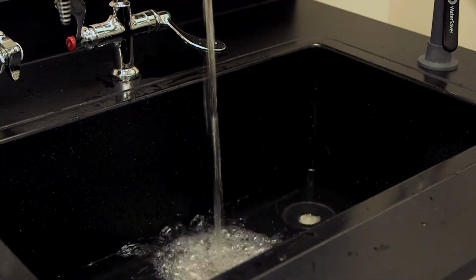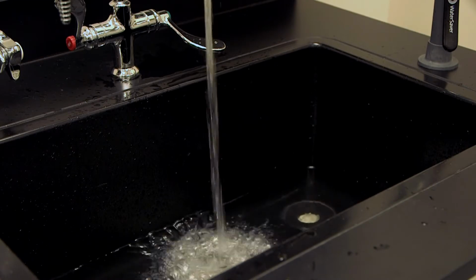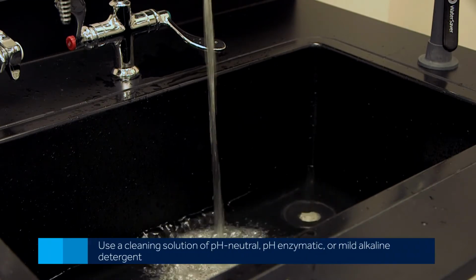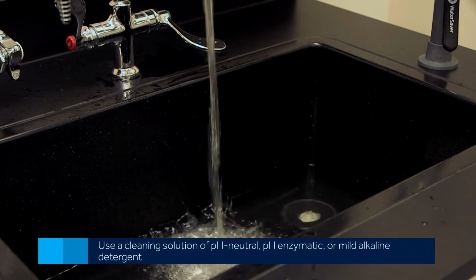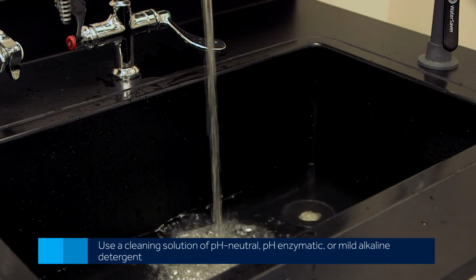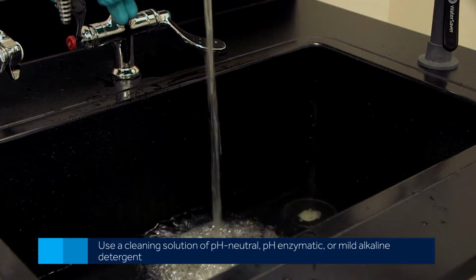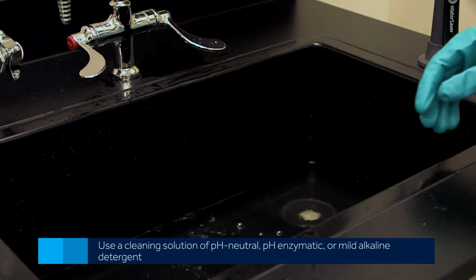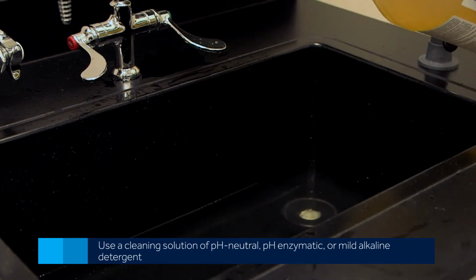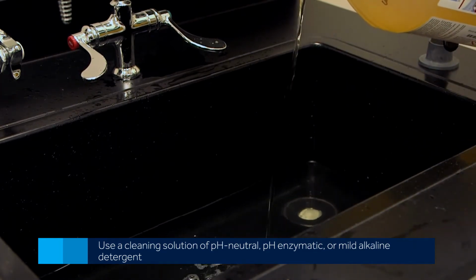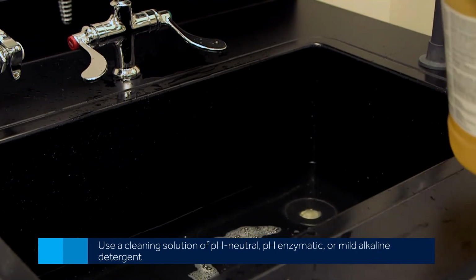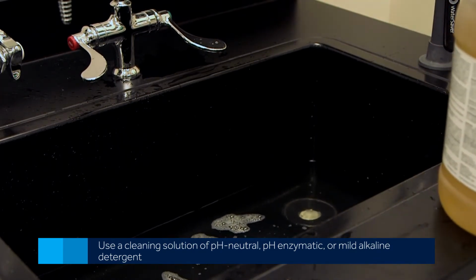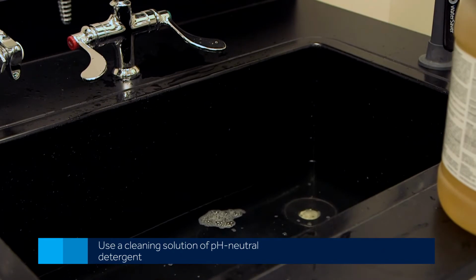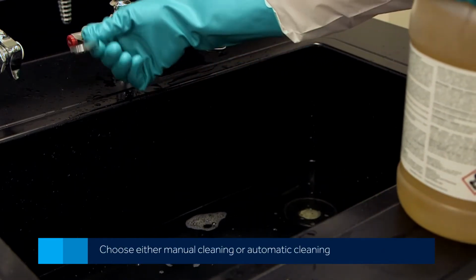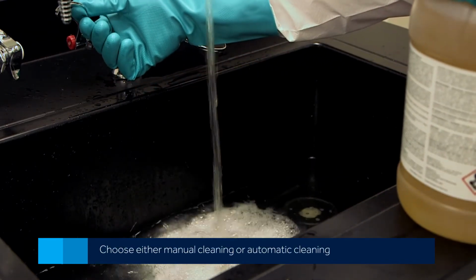Prepare a cleaning solution according to the manufacturer's instructions. Note, use a cleaning solution of pH-neutral enzymatic, or mild alkaline detergent to clean the generator and battery insertion guides. The battery insertion guides and the generator are tested for material compatibility with cleaners that have a pH range from neutral to 10.9. Choose either manual cleaning or automatic cleaning.